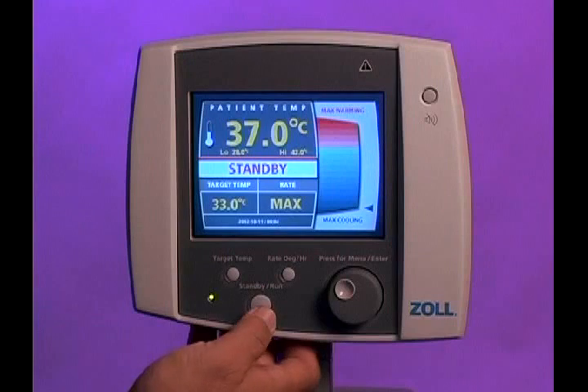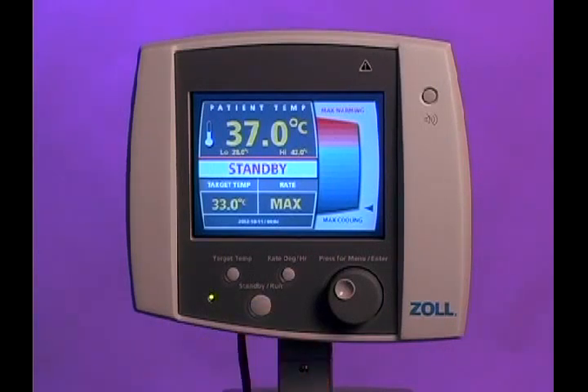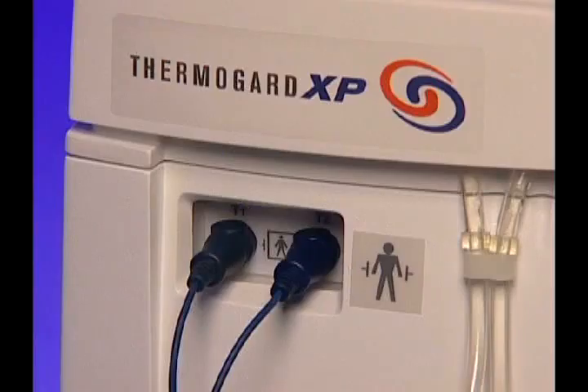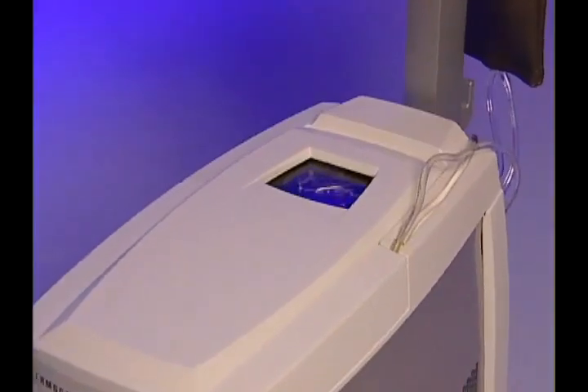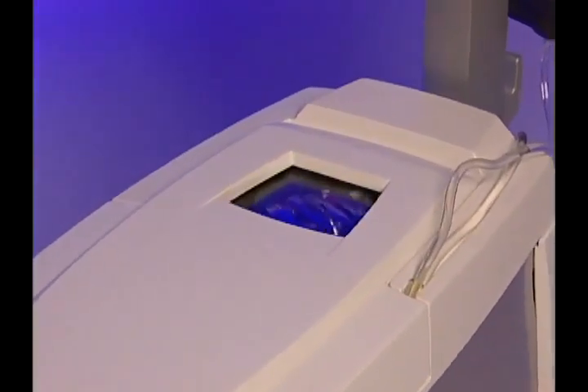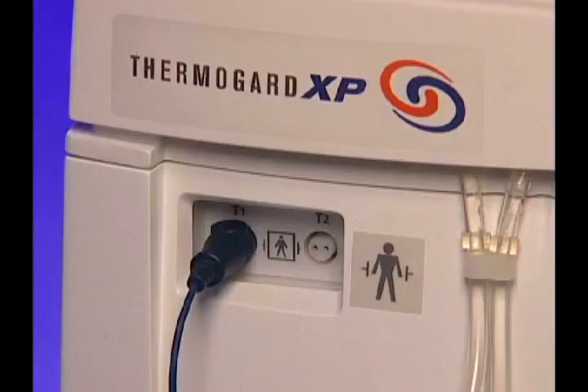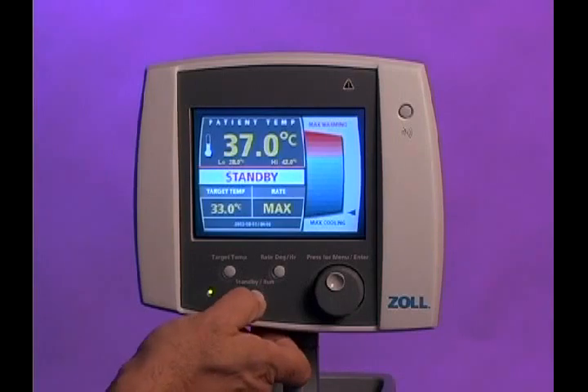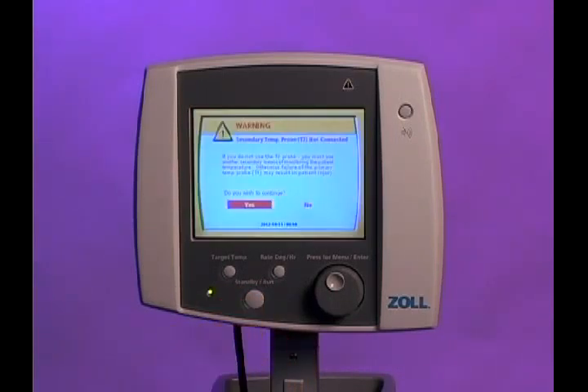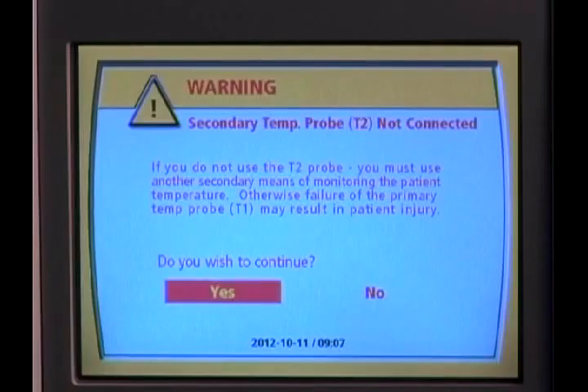To begin patient treatment, press the Standby Run button. If there are 2 patient temp probes connected to the system, it will immediately go into the run mode and patient treatment will begin. However, if only 1 temperature probe is connected to the system when the Standby Run button is pressed, a warning screen will appear. This is to remind you that patient injury may result if only 1 probe is used to monitor patient temperature.